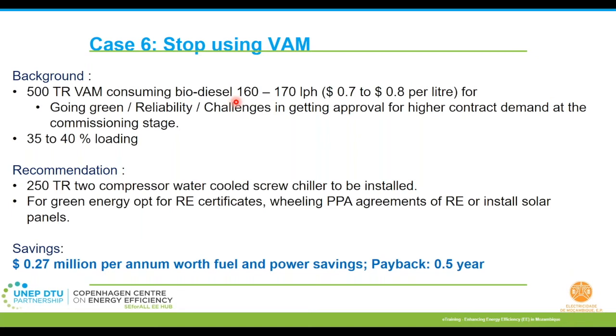They also had challenges initially, when setting up, in getting enough contract demand from the utility company at the commissioning stage. So yes, it makes sense. But 9 to 10 years down the line, they are still maintaining the same setup, even though they have got all the approvals from the utility company and the contract demand was increased. When we went to do the study, we found that it was barely loading about 40 to 50% of its capacity.